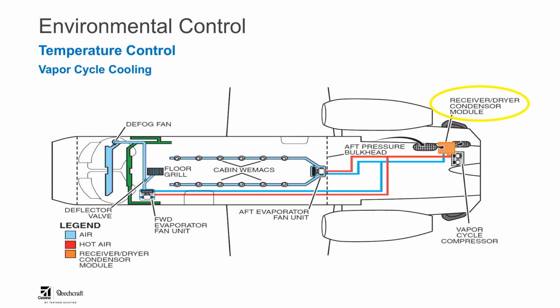And sometimes if you have problems with the air conditioner cycling on and off, especially if it's frequent, as in less than a minute and then it'll kick back on, go back and check the outflow of that condenser module outlet. Often, if the condenser fan is not working, you won't feel any flow coming out of there, and that will cause the system to cycle on and off due to the pressures not being where they should because the condenser is not working correctly. So that's something you can look for if you have air conditioner cycling issues.